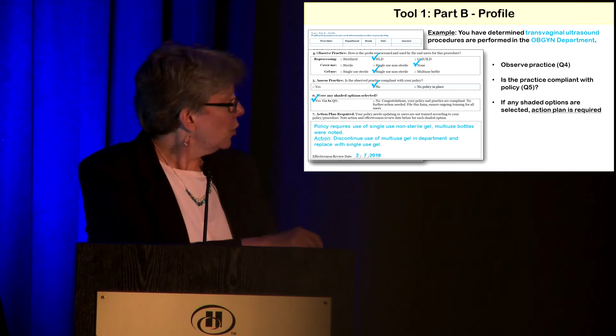All right, tool 2 is the algorithm. It's based on the Spaulding classification, as Roy was describing before, and I'm going to describe again. Referenced by the CDC guidelines, AAMI, ANSI, CMS, and Joint Commission. This system dictates that the level of disinfection or sterilization a device should be subjected to is based on the degree of infection risk associated with its use and contact in patients.